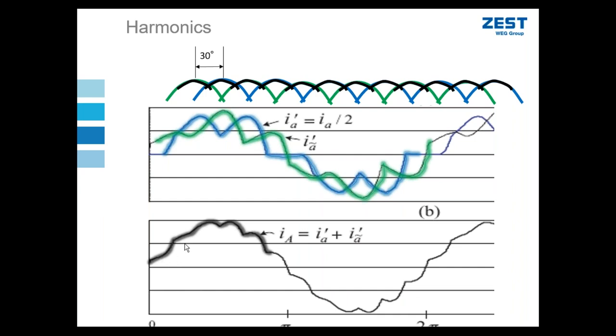And that shows it there. So this phase shift technique is commonly used in medium voltage drives, not so much in low voltage drives, because generally the total megawatt installed base of medium voltage drives is always going to be large. So you're never going to put in a 55 kilowatt medium voltage drive. It's always going to be a couple of megawatts. So the designer of the medium voltage drive system needs to take cognizance of harmonics right from the get-go, because it's pretty much guaranteed that if you don't, you're going to have an issue with harmonics on your system.